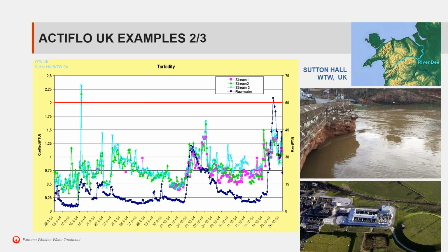Also confirming the design loading rates, we generally design plants around 40 metres an hour based on the footprint. We didn't really do anything with the upstream coagulation and maturation tank, other than developing our own enhanced coagulation system, and we were using static mixers upstream of the Actiflo, particularly to mix the coagulant chemicals.